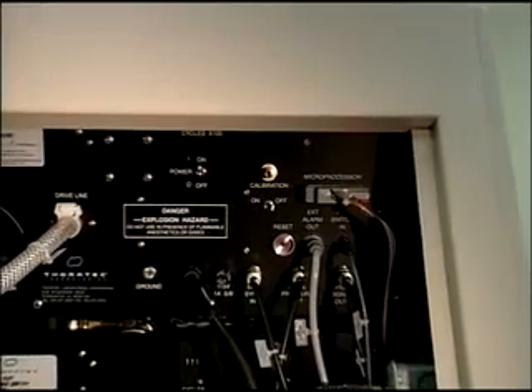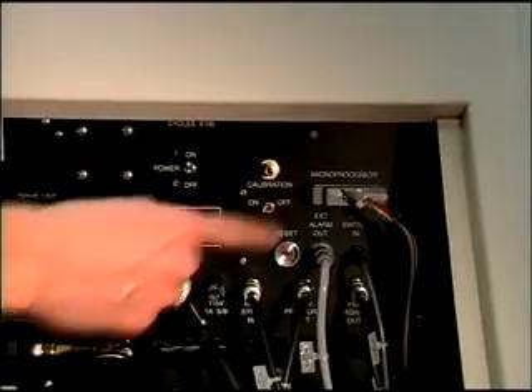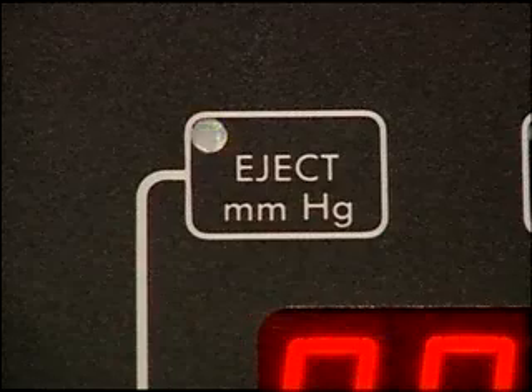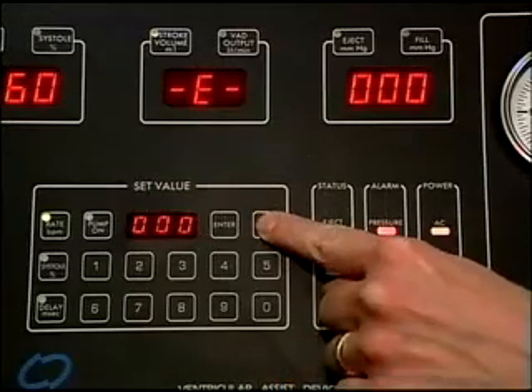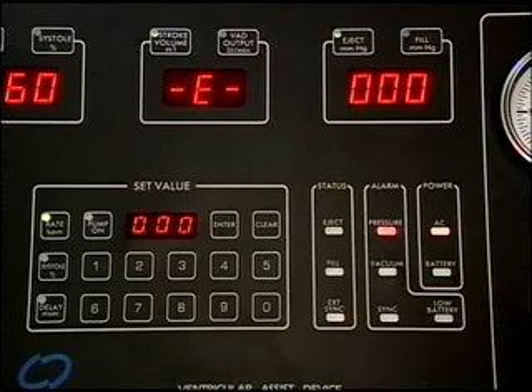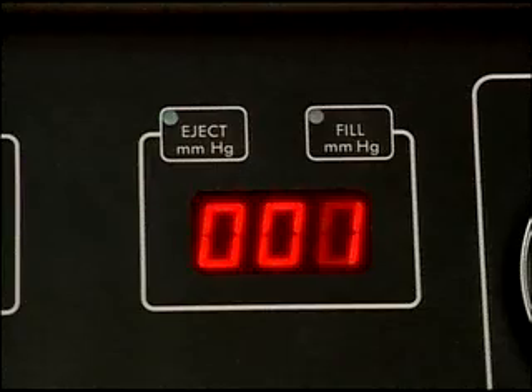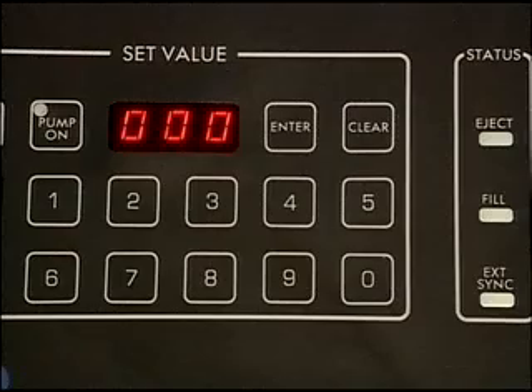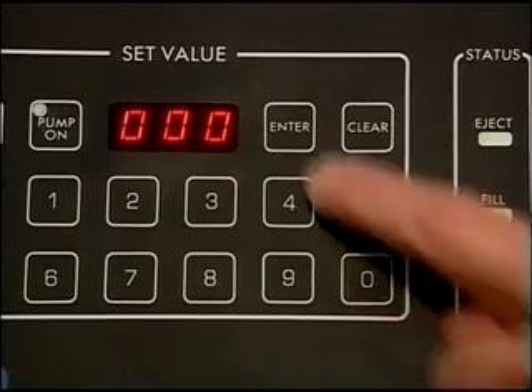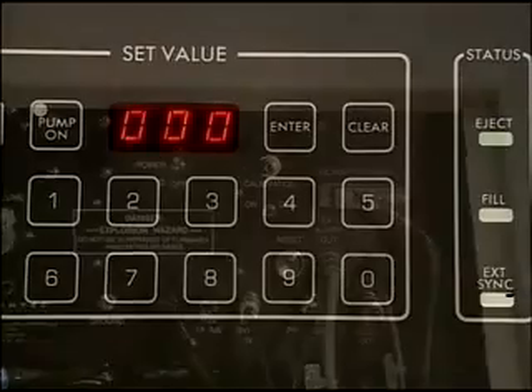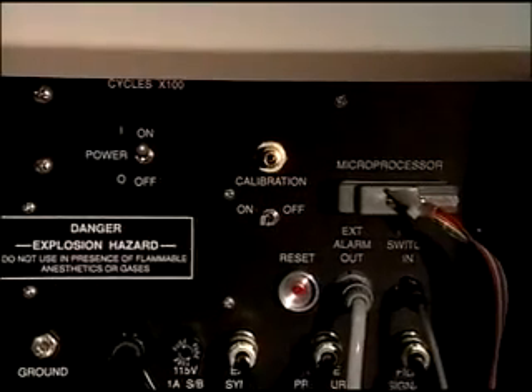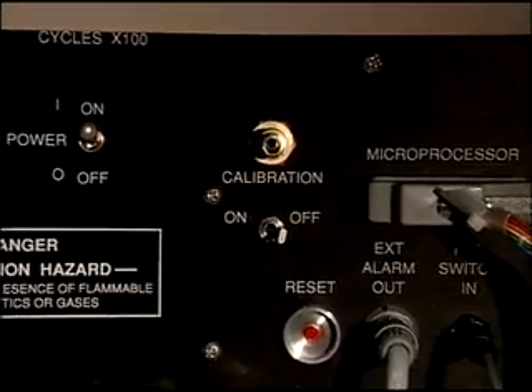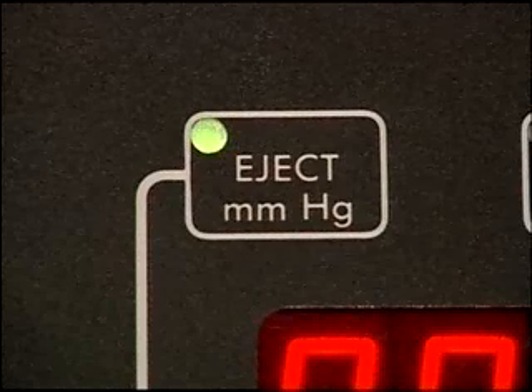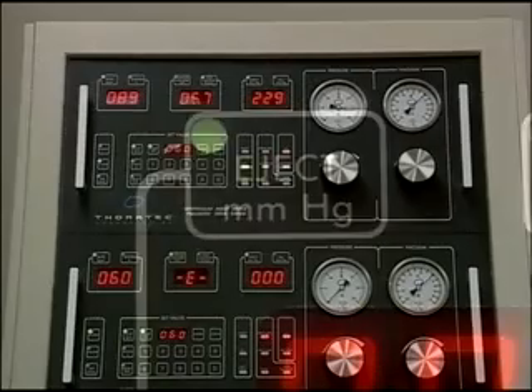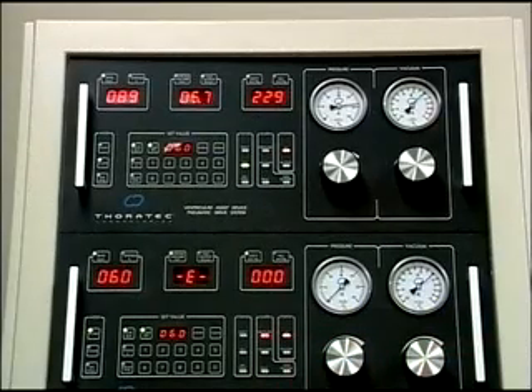To begin console calibration, move the calibration switch on and verify that the pressure eject fill indicator light flashes. Press clear, then enter on the front panel. The set value and eject fill displays should read 000 plus or minus 1. If not, press 000 on the console keyboard, then press enter. This completes the calibration phase. Turn the calibration switch to off, then verify that the pressure eject fill indicator light has stopped flashing. Now repeat the calibration process for the second drive module.